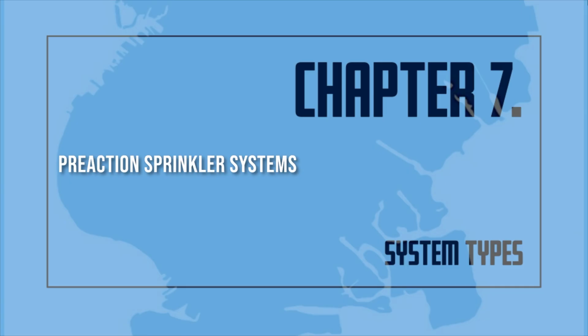Other ways to activate a pre-action valve are smoke detectors, gas detecting systems, hydraulic, electric, manual release, and automatic signals from other safety systems. Alarms are standard accessory equipment on water control valves. They provide an audible signal in the building if the valve operates for any reason. An alarm is also sent out if a problem is discovered with the equipment. The alarms send a signal to a central station company or a public fire alarm system. Often the signal is sent to both the central station company and the public alarm.